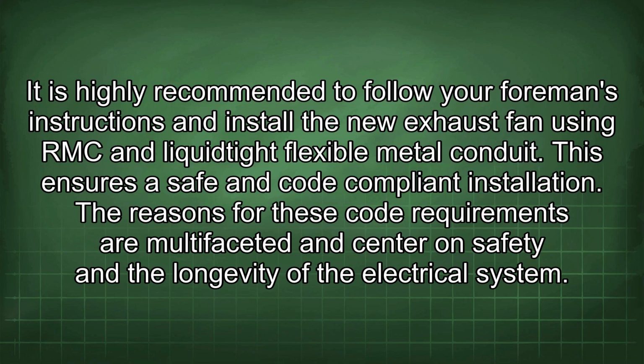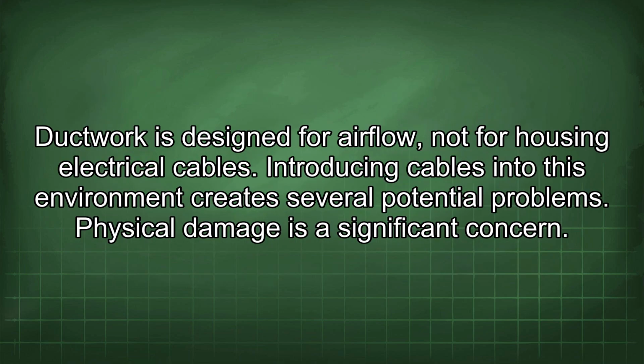The reasons for these code requirements are multifaceted and center on safety and the longevity of the electrical system. Ductwork is designed for airflow, not for housing electrical cables. Introducing cables into this environment creates several potential problems. Physical damage is a significant concern.